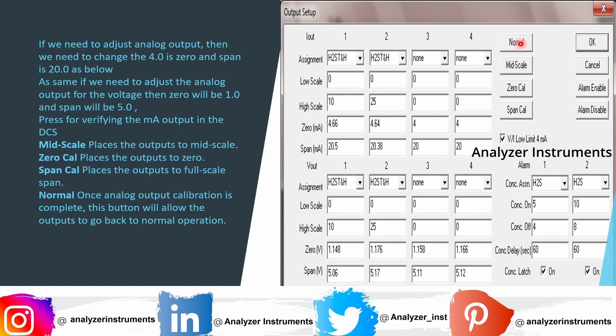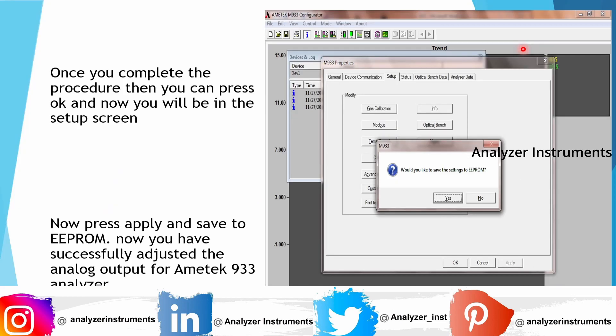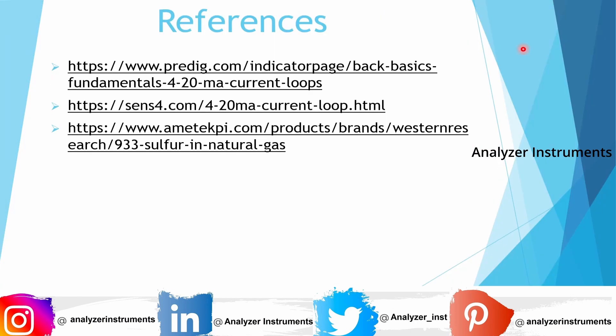Once you have adjusted everything, don't forget to press Normal — the analyzer will return to normal operating position. After completing the procedure, press the OK button and the Setup screen will appear. Once you press Apply, it will ask whether to save to EEPROM — press Yes to save. These are the references used to make this video.